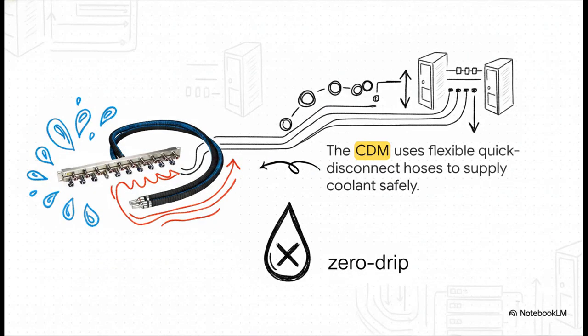Now, once that liquid absorbs the heat from the chip, it obviously has to go somewhere, right? It gets handed off, kind of like a relay race, to the coolant distribution manifold, or the CDM. You can think of the CDM as the vital plumbing for the server rack. It supplies the frigid liquid to those cold plates and then safely returns the hot liquid away from the servers. And because data centers are absolutely mission critical, these use quick disconnect, flexible hoses with single-handed zero-drip connectors, meaning operators can service a liquid-cooled system totally safely without any fear of spilling water onto millions of dollars of computing equipment. That would be a total nightmare, obviously.